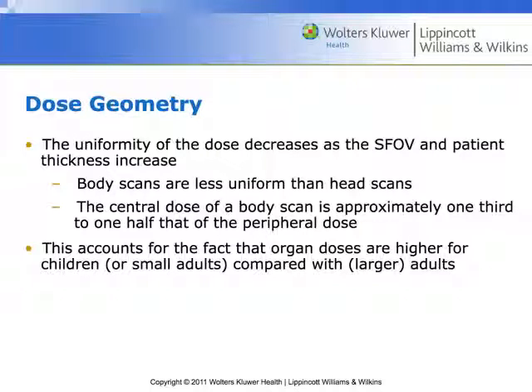Body scans are going to be less uniform because the body is essentially elliptical in shape when viewed in a transaxial plane. The central dose of a body scan will probably be about one-third of what it is at the skin. The head has a fairly uniform density and is more or less circular, so we see more or less equivalent doses across the surface of the skull and a very similar dose at the center.